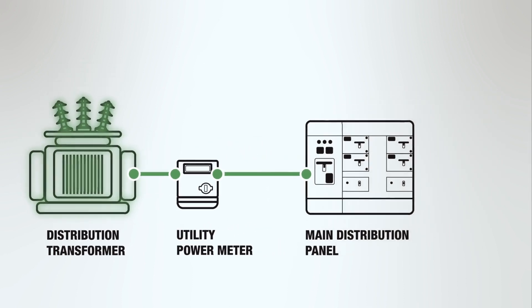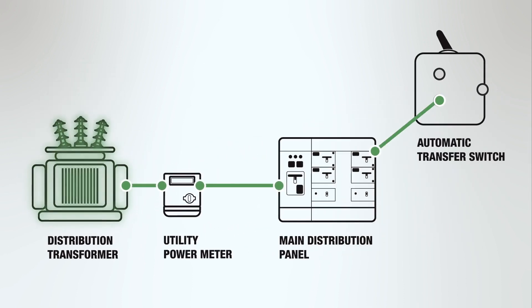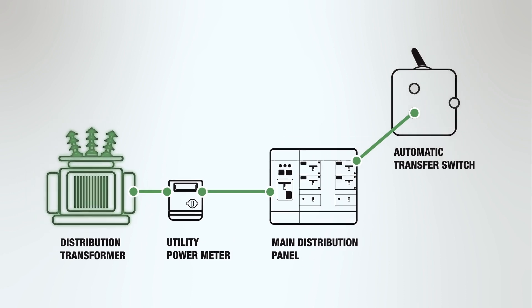The main distribution panel connects to an automatic transfer switch, or ATS, which looks for utility feed disruptions and power quality that is outside of specified limits.